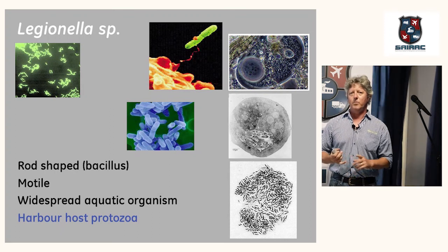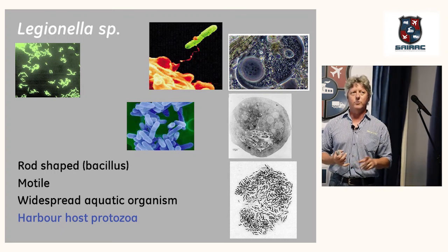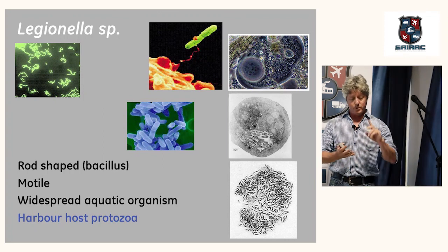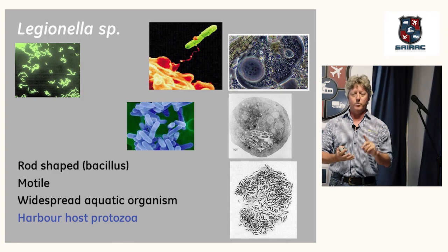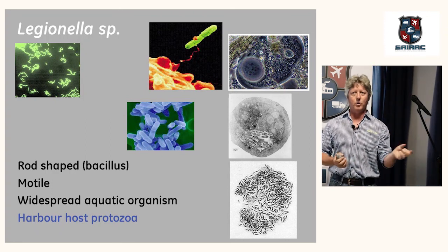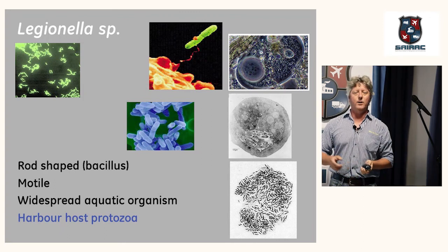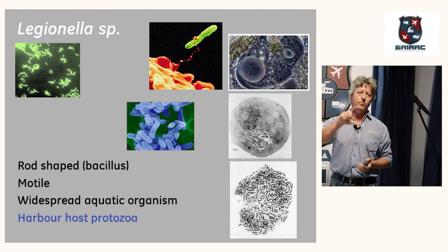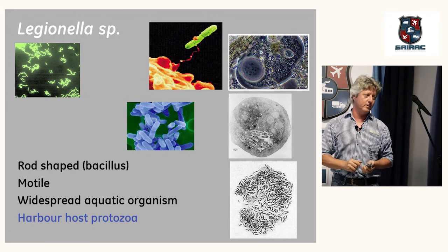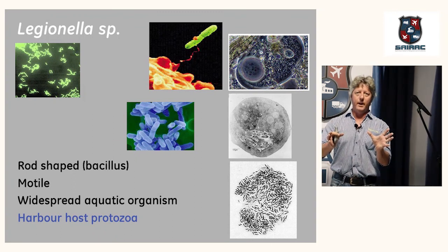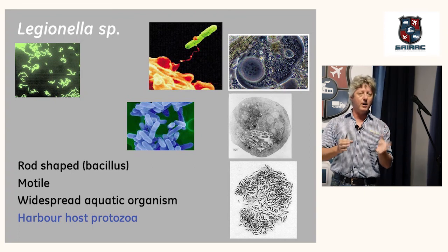Okay. And also testing. I was involved with a casino where we tested the water in all the cooling systems. We even went as far as testing the water in the rooms. Hot water, cold water, hot water coming from geysers. And on one spot, we found a Legionella sample that tested positive. We then had to isolate that system and then run it through with very high chlorine levels.